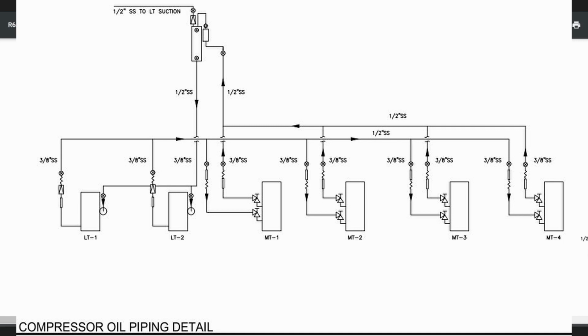Most people might not know this, because most of our audience is commercial supermarket technicians. With liquid refrigerant and oil, usually liquid refrigerant will stay on the bottom, and oil will stay on the top, just like oil and water. With ammonia, it's different. The actual ammonia will sit on the top, and the oil will actually sit on the bottom. And is that the reason why you basically put the oil purge line on the bottom of the heat exchangers, Ed? The oil in an ammonia system, when it's in liquid or any other state, will always be on the bottom.